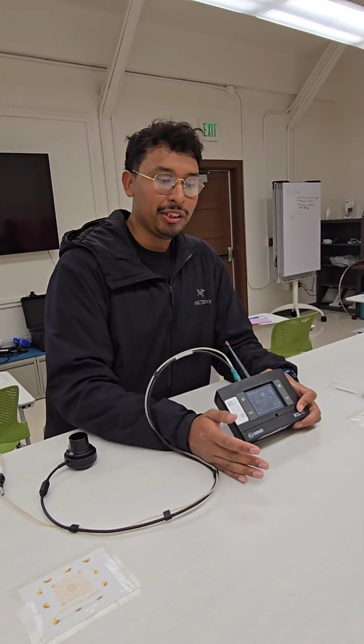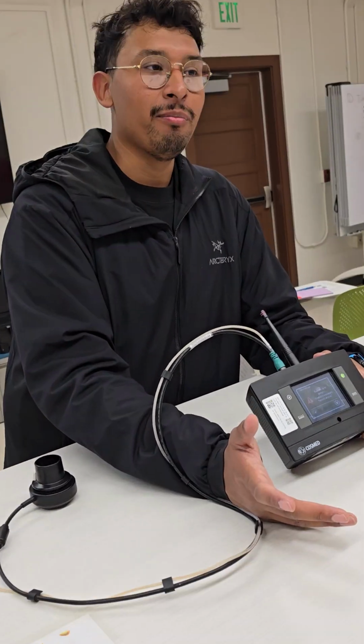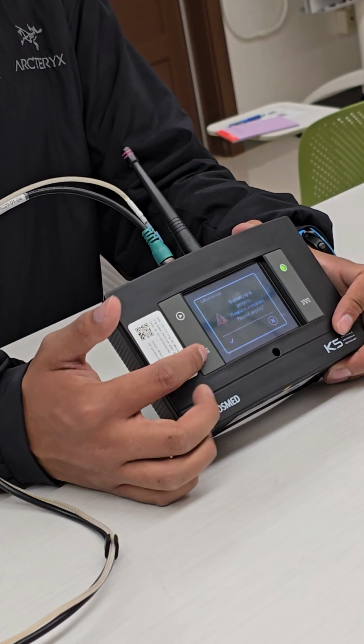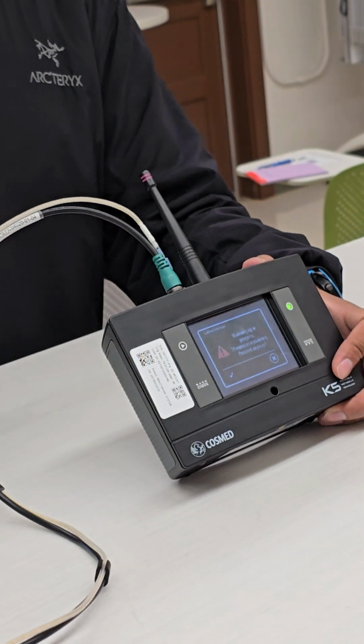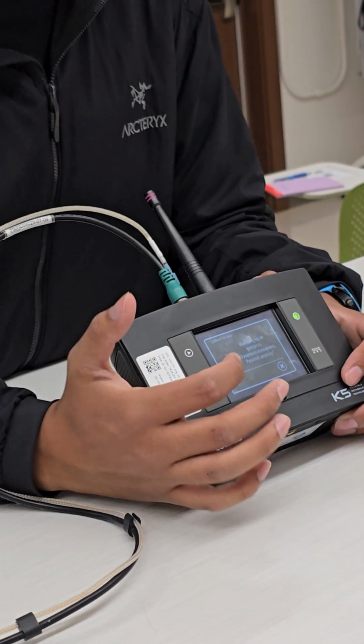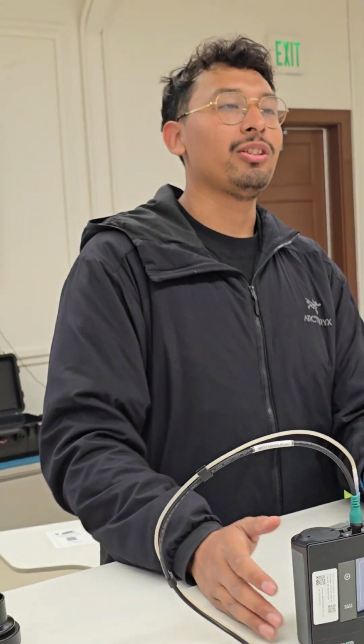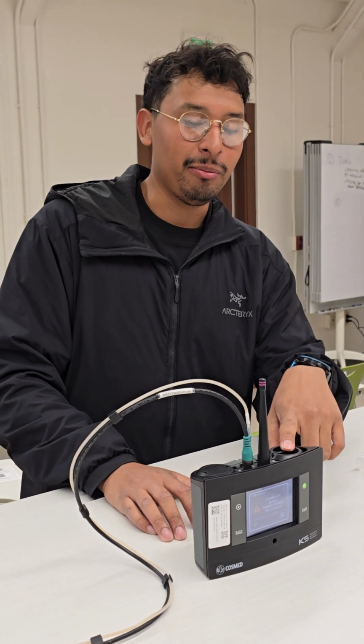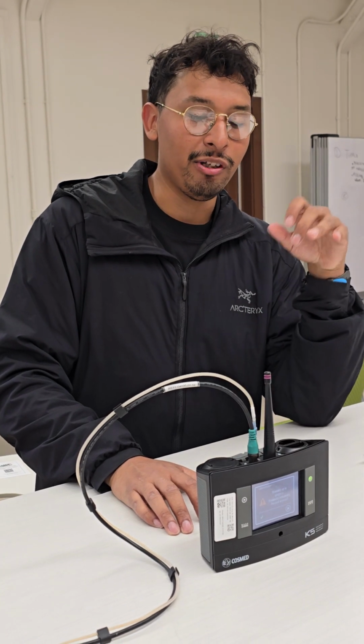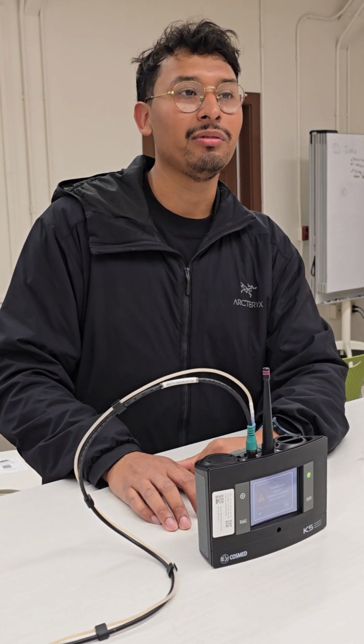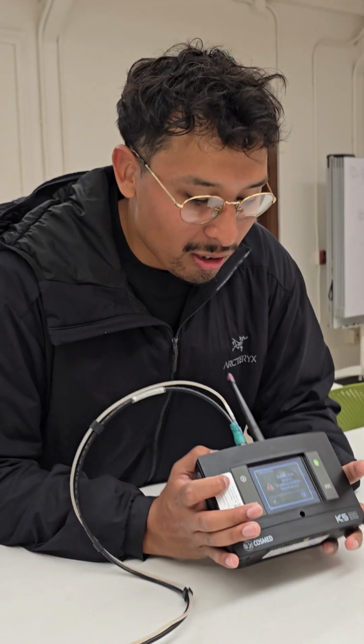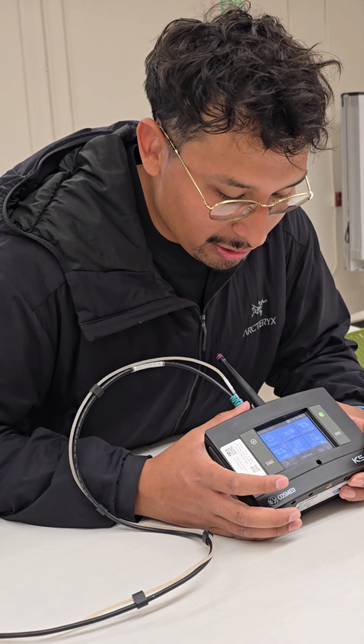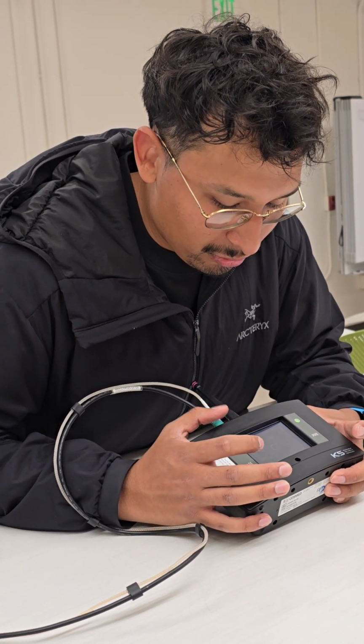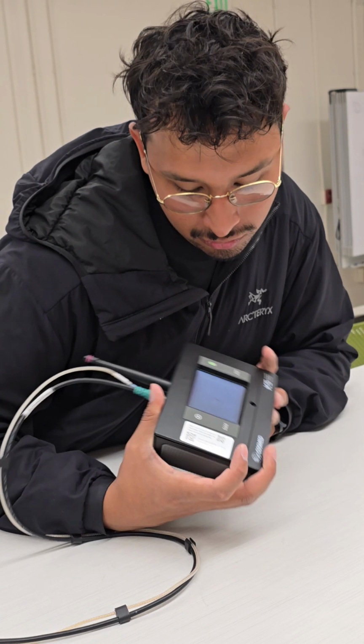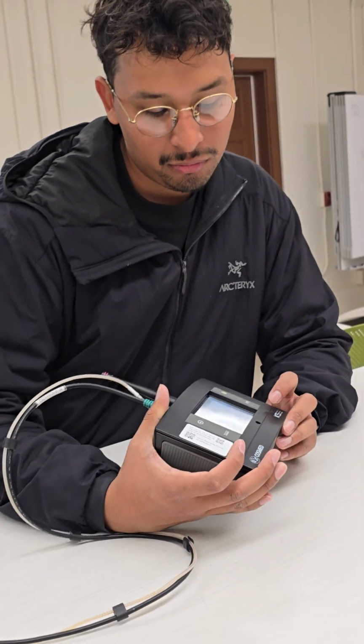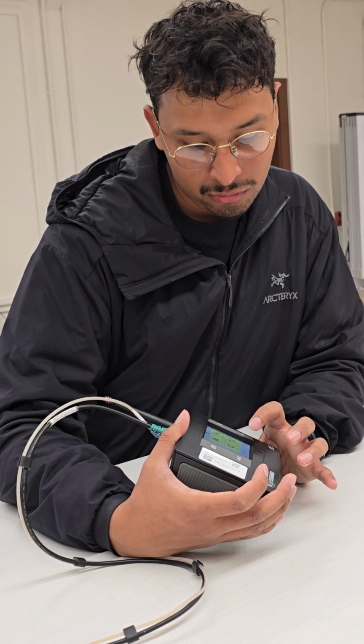If that ever happens to you guys, if you had the K5 out for like 5 minutes, it's fine. The analyzer is still warm. It's just that the system is like, you just powered me on, you need to wait. This is basically what it's telling you. What's the normal wait period? So for a mixing chamber, if you're using a mixing chamber with a K5, it's a 30-minute warm-up. If you're doing breath by breath, it's going to be an hour. So either one of those are warm-ups. I'm going to go ahead and skip this and there we go. Oh my gosh.